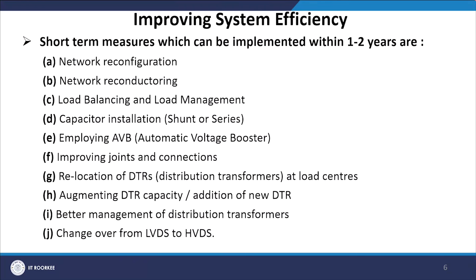Short-term measures implementable within 1 to 2 years include network reconfiguration and re-conducting to reduce losses, load balancing and load management, capacitor installation, deploying automatic voltage boosters, improving joints and connections, relocation of distribution transformers (DTRs) to load centres, augmenting DTR capacities, adding new DTRs, and better management of distribution transformers.